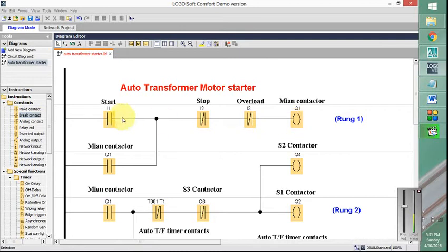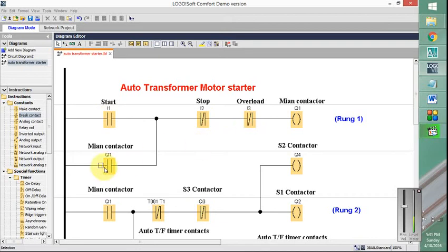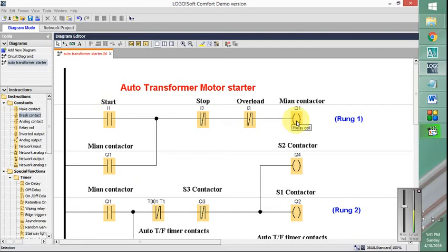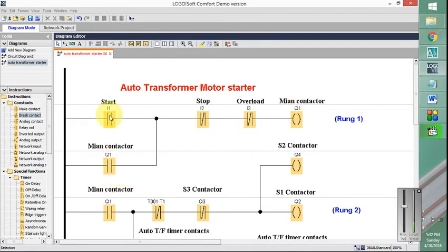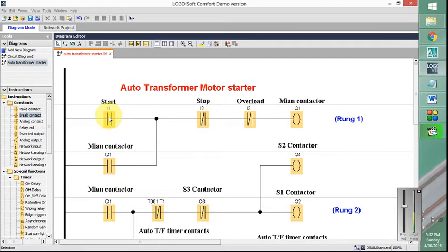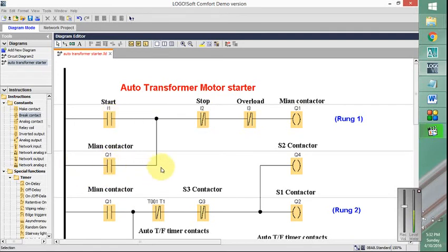It depends on the start button, stop button, overload relay, and this parallel main contactor input. The reason for adding this main contactor input in parallel to this one is to make this a momentary push button. So once this is pressed it will be energized, then if it is released this path will provide the current and keep the contactor energized.